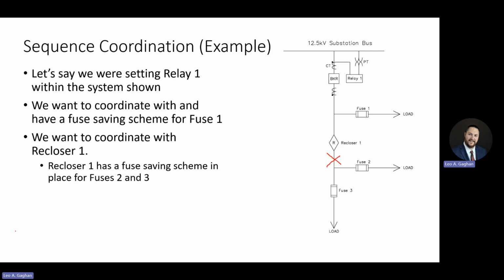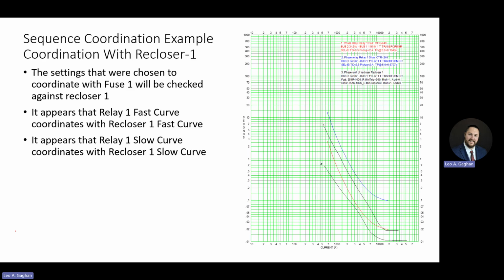So what would happen here, if we can coordinate this with our reclosing, is that a fault would happen on the designated X point that we have here. The recloser would trip. The relay wouldn't trip, but it would actually pick up. And when it picks up, it would skip a shot in its reclosing cycle. So both the relay and the recloser would go from shot 0 to shot 1. And they would be able to increment in sequence with each other, so that they can stay on the same page. So that when recloser 1 moves to its slow curve, relay 1 can also move to its slow curve. In the two time current curves, curves 2 and 3 can then coordinate.